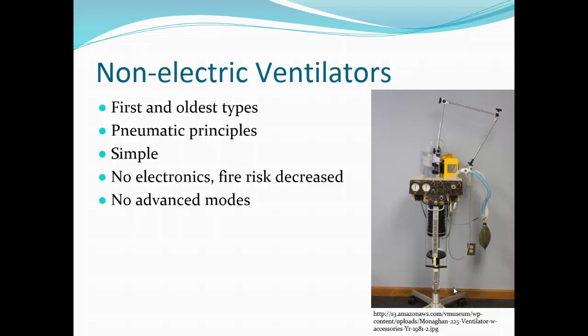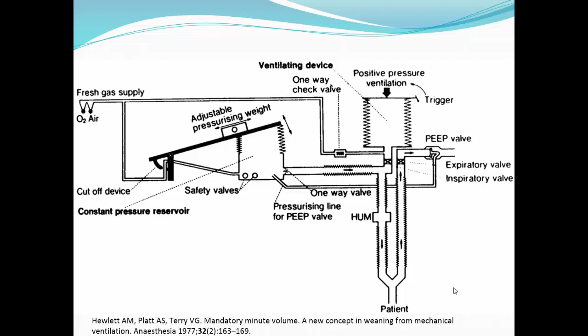Here it's designed by a system of bellows with an adjustable weight that you can slide up and down to keep the springs to basically set your pressure. You can set it up to about 15 centimeters of pressure. And then your patient's here, and as you take a breath, the ventilator senses it, releases the pressure, and you deliver a pressure of 10 to 15 centimeters with your corresponding tidal volume. You exhale out, you have your PEEP valve there to maintain positive pressure during treatment.